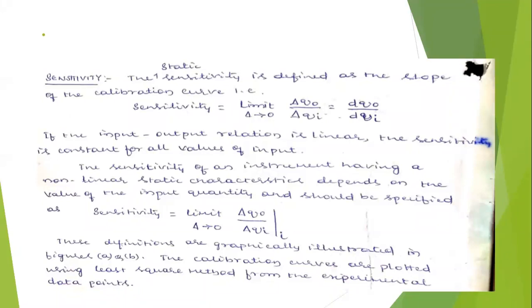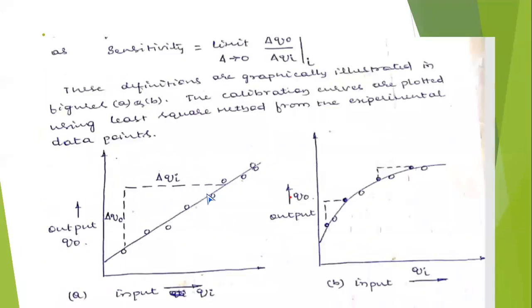How do you define sensitivity? From this graph, just to understand, all of you observe here you have two curves. That is called the calibration curve. This is called the calibration curve. For example, 0 to 50 micrometer, or 0 to 100, or 0 to 250 micrometer.